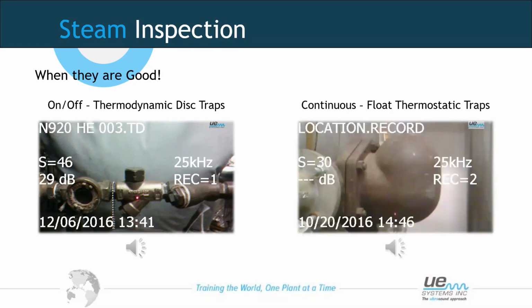If we then go on to a continuous flow trap, a float thermostatic trap, for example, that will deal with higher levels of condensate, we would expect to hear a steady flow of turbulence on this. Now, for example, in this one here, we're going to have a metal ball. It could be a free float or it could be on an armature. Now, we might expect to hear on a free float, for example, the metal ball inside knocking about within the body. So if we hear that, that's fine, but we want to be listening for the turbulence inside as well.